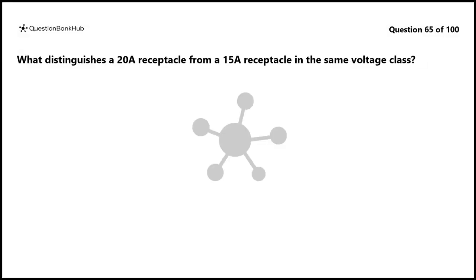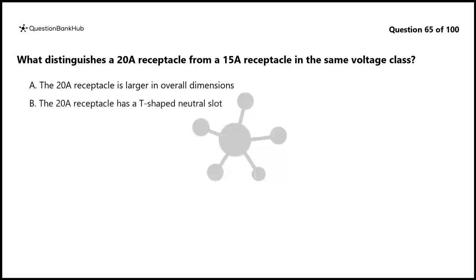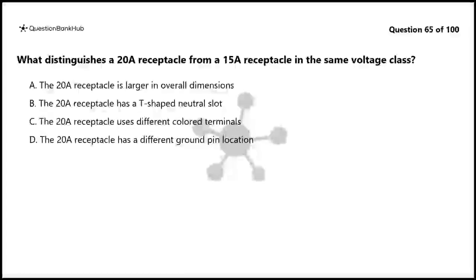Question 65. What distinguishes a 20 amps receptacle from a 15 amps receptacle in the same voltage class? A. The 20 amps receptacle is larger in overall dimensions. B. The 20 amps receptacle has a T-shaped neutral slot. C. The 20 amps receptacle uses different colored terminals. D. The 20 amps receptacle has a different ground pin location.